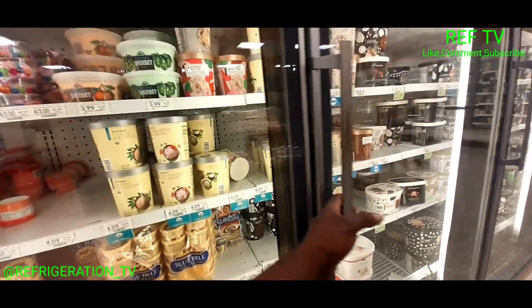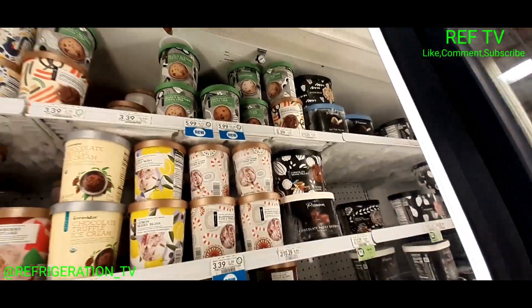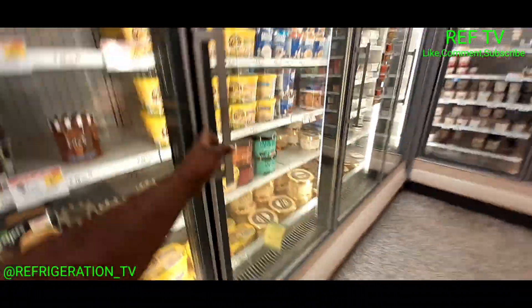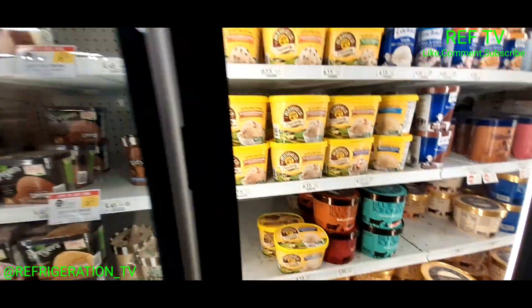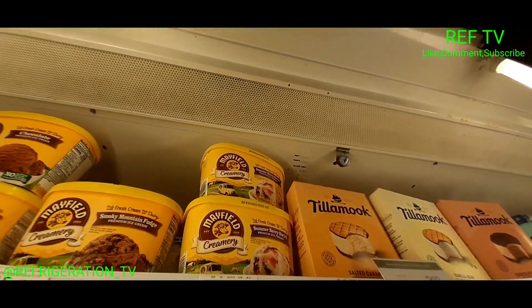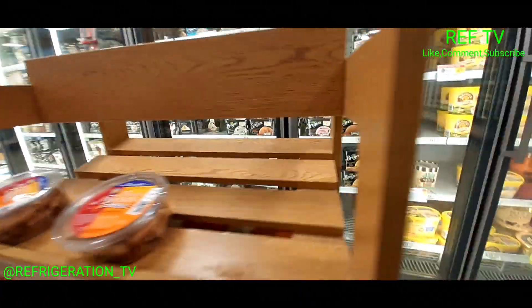All this ice cream is warm. Let me set my tool bag down — fans are not running. Let's check this case, it's the same circuit. Look at that, they got water on the floor. Slip and fall hazard. No fans running in this case — it's rack two, circuit one B. Let's put something here in front of that so no accidents, no slip and falls.